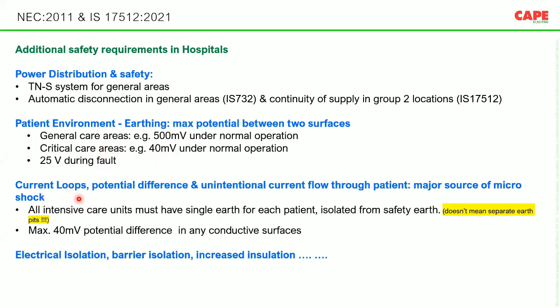The next part is current loop. Potential differences and unintentional current flow through patient. So this is actually a serious issue in a hospital. Here, what you should do is all intensive care units must have a single earth for each patient, isolated from safety earth. So this is actually a system which is recommended for hospital.